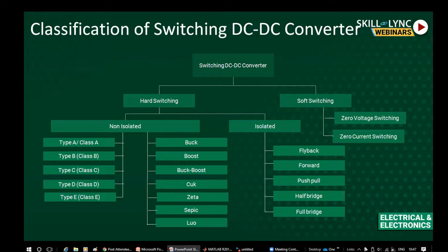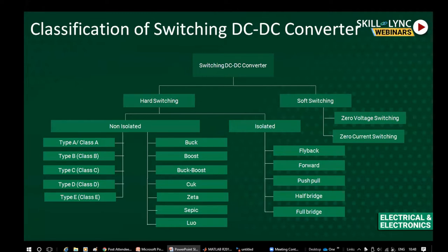To reduce those losses, we switch the devices either at zero voltage or at zero current — this is nothing but soft switching. In soft switching converters, we use resonant components L and C, designed such that the switch can be turned on at zero voltage or turned off at zero voltage or zero current. During turn-on and turn-off, the device voltage or current can be zero. In hard switching converters, no resonant components are used during turn-on and turn-off.